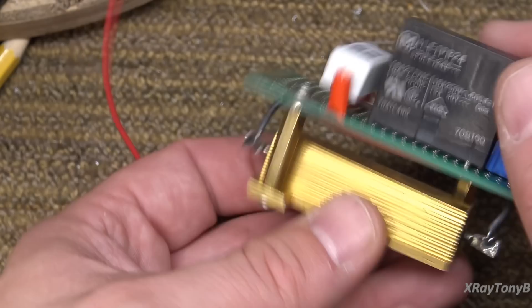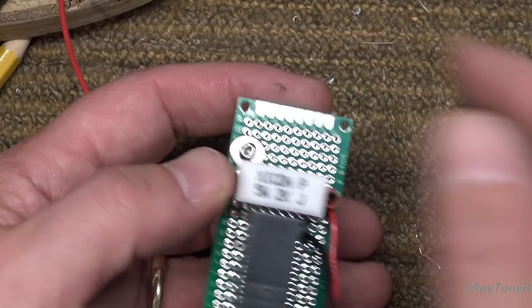Here's your 5 watt 2K dropping resistor. This has to be a little bit larger sized resistor because the coil of the relay draws some current, maybe 20 milliamps or so. You're going to need to be able to dissipate that current through this resistor. So at 5 watts, this is not going to get warm at all. You could actually get away with less. I tested this with a 1 watt or a 2 watt resistor, and it barely got warm. So this is kind of overkill, which is how I want it. Now, we have to determine this value. This is not going to work with every relay. It will work if you buy this relay.